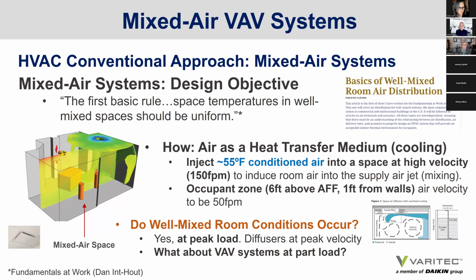So in a conventional mixed air system, in order to move energy, our first goal and objective is to create, per ASHRAE guidelines, a unified thermal condition throughout the cubic volume of space within plus or minus 2 degrees. To achieve that, we inject high velocity 55-degree air through diffusers. That high velocity air creates a negative pressure zone that induces room air into the supply air jet, allowing mixing to occur. Well, the question is, do well mixed room conditions actually occur? Well, they can at peak load.